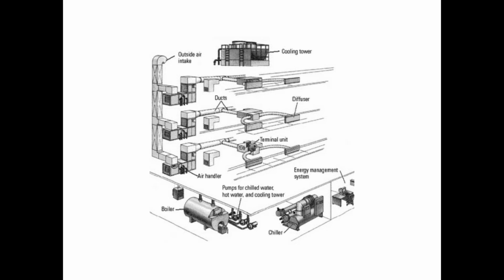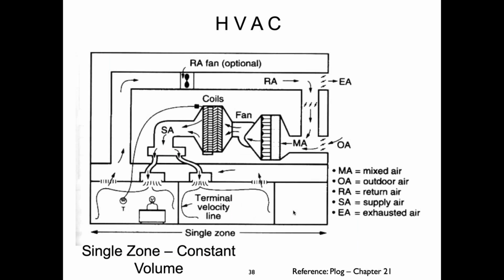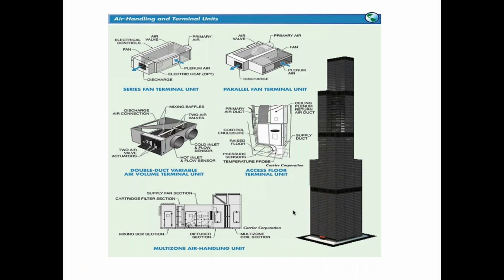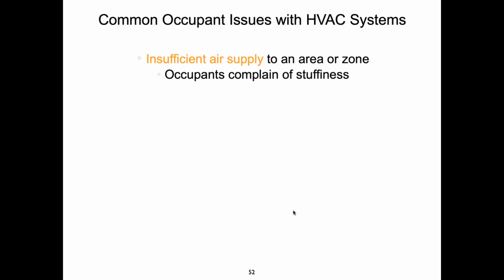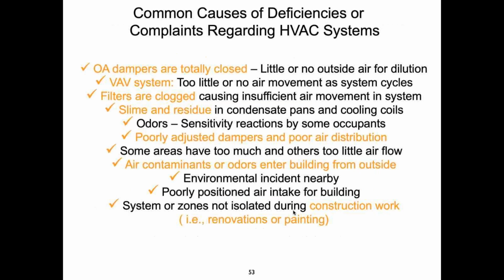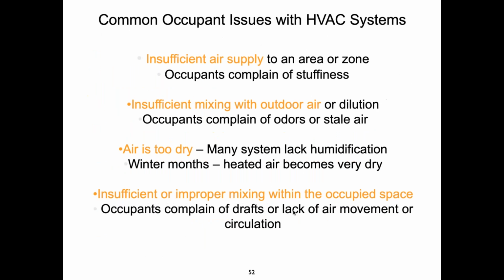You take that hot water that's taking the heat away from your Freon, it goes into your machine at 85 degrees roughly. It comes out of your machine at about 95 or 100 degrees. You need it at 85 degrees again. How are you going to do that? Well, the way that you do that is you send it to a cooling tower. I'll come back to those. Hopefully I got pictures of cooling towers here. There was one.